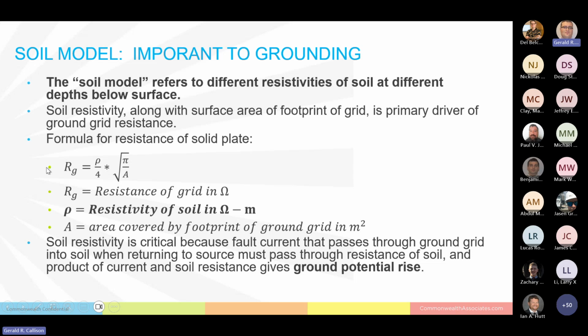This is a rough formula for a solid plate, but it's a formula we use a lot in grounding design to give a quick, dirty estimation of what we're expecting for a grid resistance. It's not something you should really memorize per se, but the resistance of this plate is equal to the resistivity divided by 4 times the square root of pi over the surface area of the footprint of the grid. What I want to demonstrate is that the resistivity of the soil and the surface area of the footprint are really critical to the overall resistance of the grounding system.